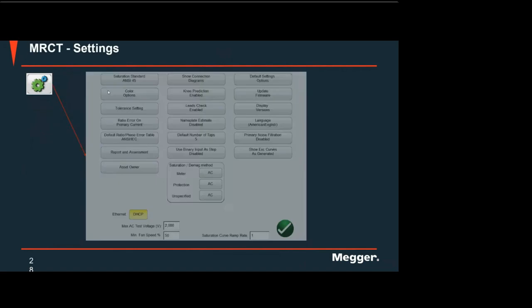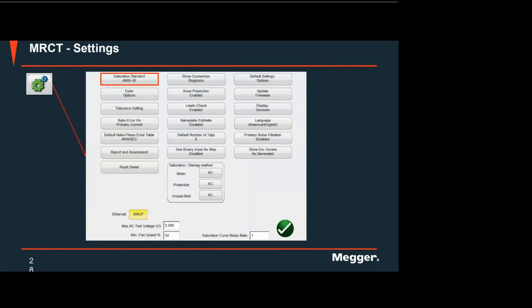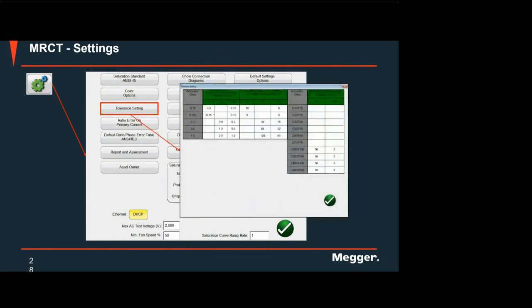So looking at the settings here, you have access to the saturation standard. If the CT is ANSI or IEEE, then you can select ANSI. If it is a non-gap core or ANSI 45, you can select the standards here, depending on the nameplate of the CT. You can change the color, you can change the tolerance setting. Of course, this is based on the standard, meaning these are the limits.